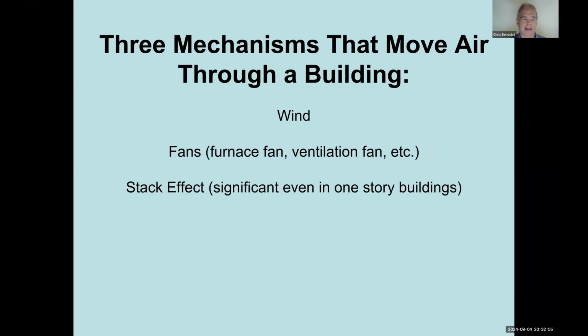And then there's the stack effect, which is hot air rising through the building like it rises through a chimney, because you heat a fluid, it gets more buoyant, it gets lighter, spreads out. And in the summer, the stack effect moves air downwards through a building. And because the temperature difference indoors and out is greater in the winter, the stack effect is much more significant in the winter than it is in the summer.